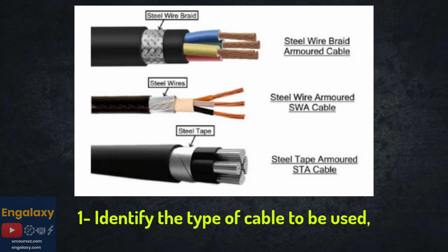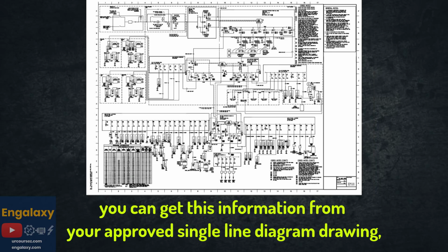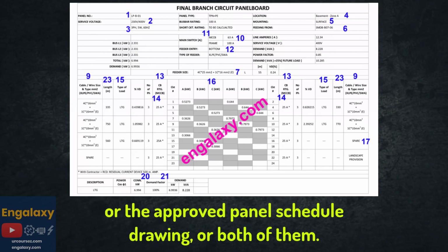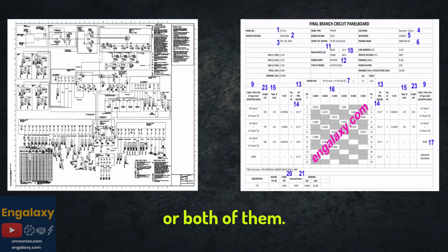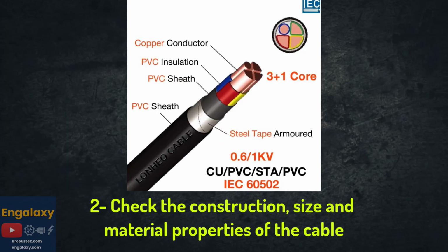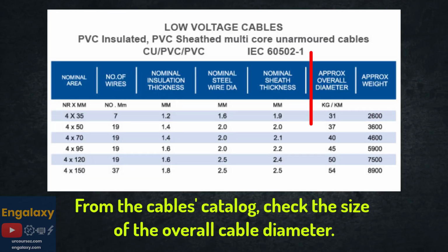Identify the type of cable to be used. You can get this information from your approved single-line diagram drawing, or the approved panel schedule drawing, or both of them. Check the construction, size, and material properties of the cable. From the cable's catalog, check the size of the overall cable diameter.